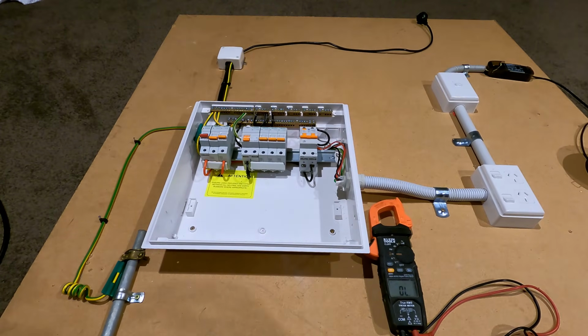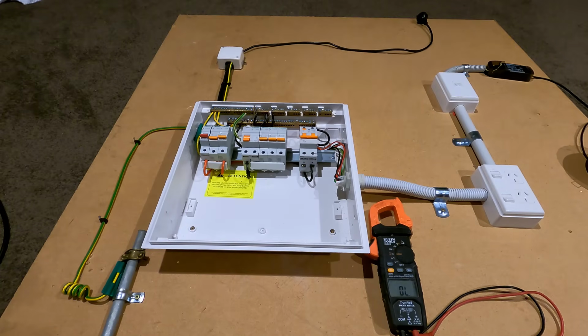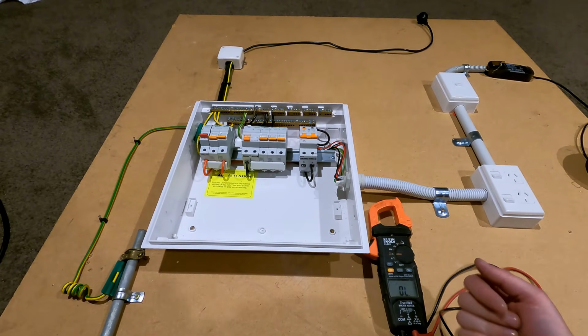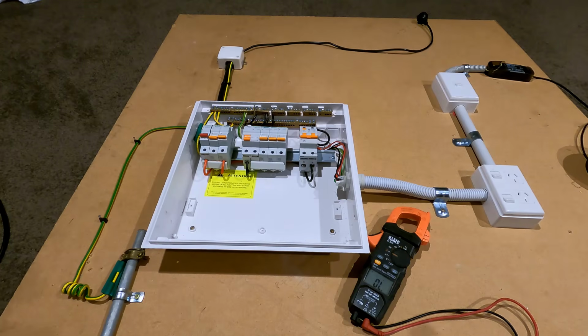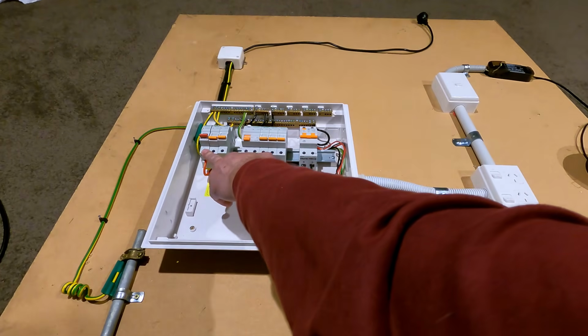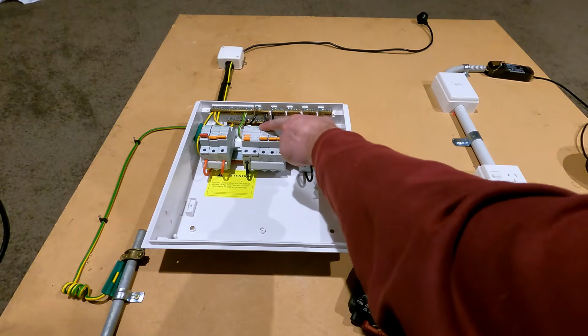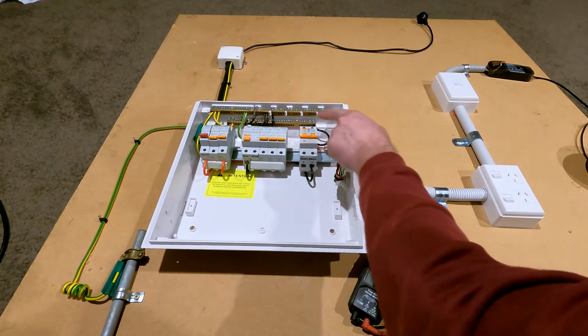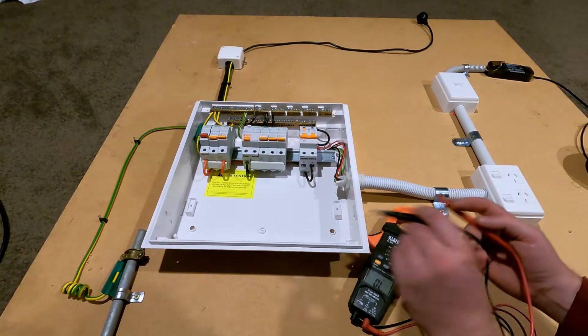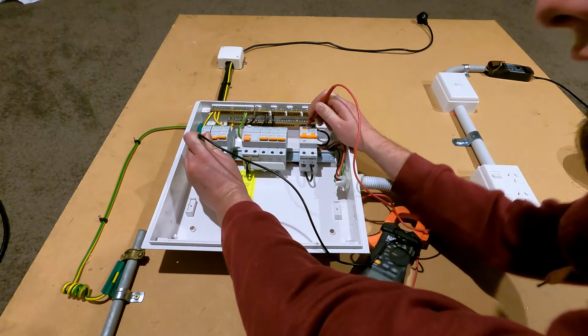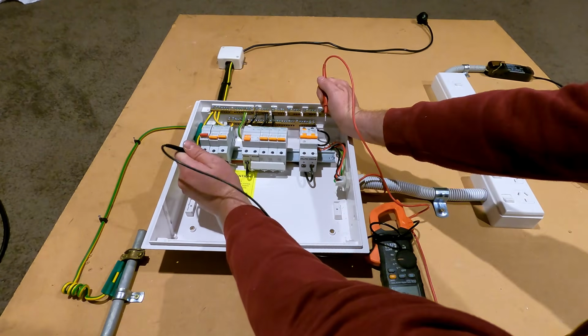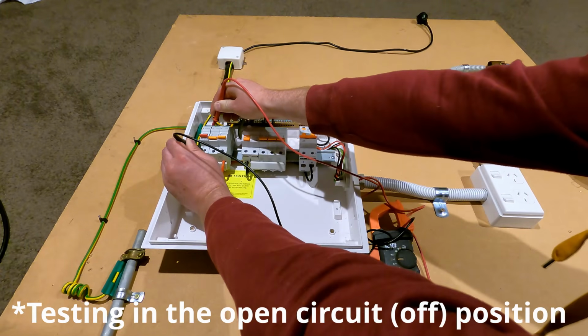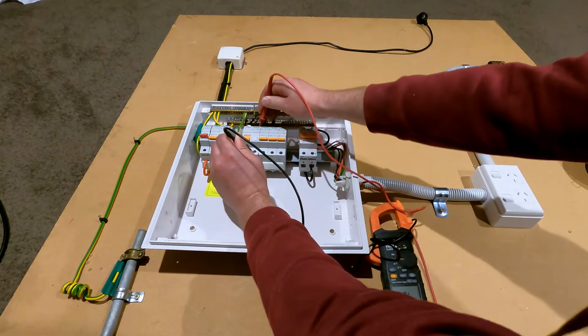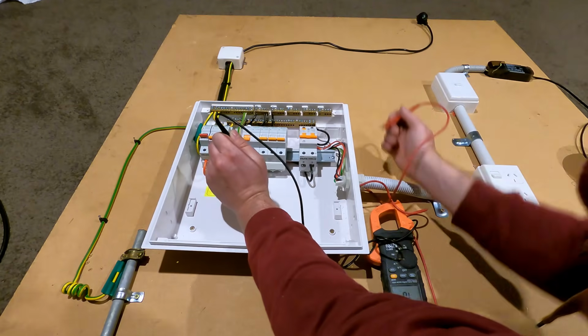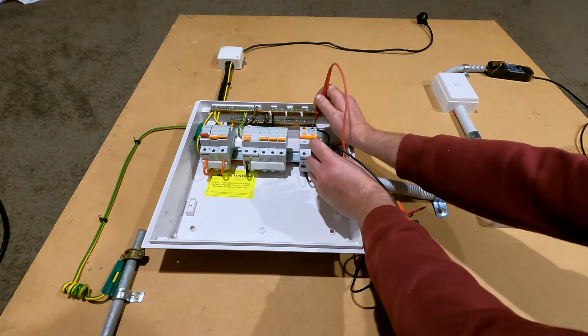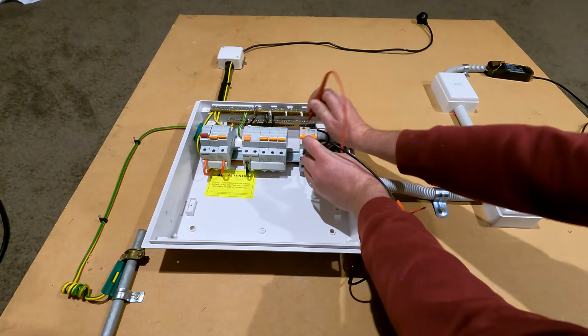The other things with circuit connections that you want to verify, that our circuits are the way we intended to wire them. So what I want to test here is that from the bottom of the main switch, we go to the line side, or the top of the RCD and the top of the RCBO. Okay, we can verify that on both of them. Now we want to test, there's no continuity there, so the main switch works. There's no continuity here, so the RCD works. No continuity, so the RCBO is working.